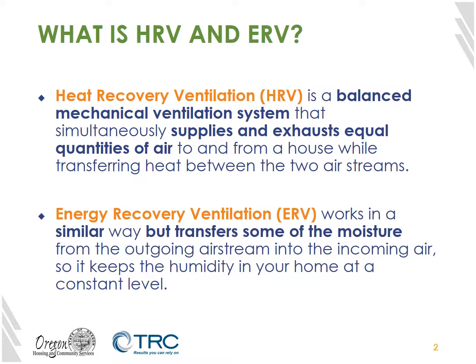We should probably start by talking about what an HRV or ERV are. An HRV is called a heat recovery ventilator, or in general, heat recovery ventilation. Heat recovery ventilation is a balanced mechanical system with equal amounts of supply and exhaust that transfer heat between the two airstreams. This means the amount of air that is brought out of the building by the ventilation system equals the amount of air being brought in, and a percentage of that heat is transferred from one stream to the other. Energy recovery ventilation works in a similar way, but also transfers some of the moisture and therefore a little bit of the additional, what we refer to as latent heat, between the two airstreams.